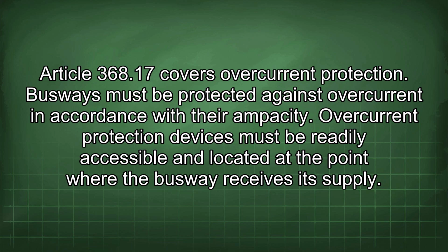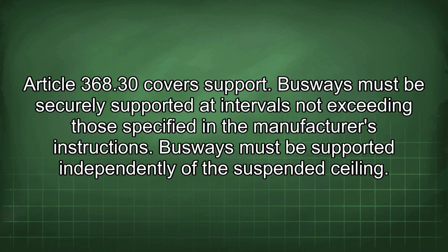Article 368.17 covers overcurrent protection. Busways must be protected against overcurrent in accordance with their ampacity. Overcurrent protection devices must be readily accessible and located at the point where the busway receives its supply. Article 368.30 covers support. Busways must be securely supported at intervals not exceeding those specified in the manufacturer's instructions. Busways must be supported independently of the suspended ceiling.